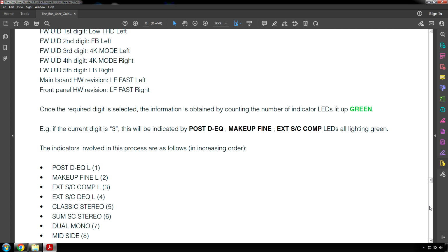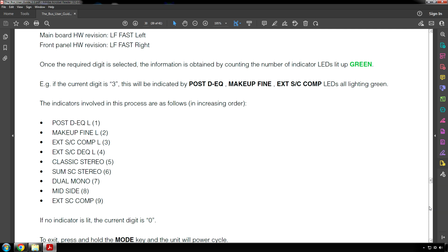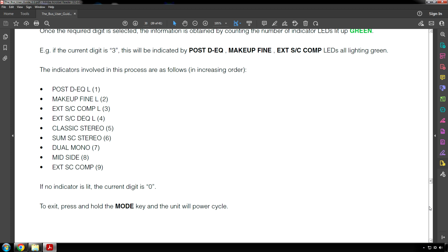Once the required digit is selected, the information is obtained by counting the number of indicator LEDs lit up green. For example, if the current digit is 3, this will be indicated by post DEQ, makeup fine, EXT-SC comp LEDs all lighting green. The indicators involved in this process are as follows, in increasing order. And you can see that on screen. If no indicator is lit, the current digit is 0.